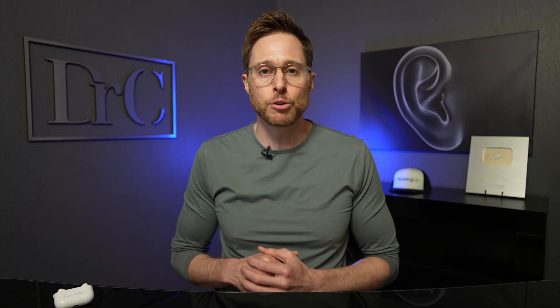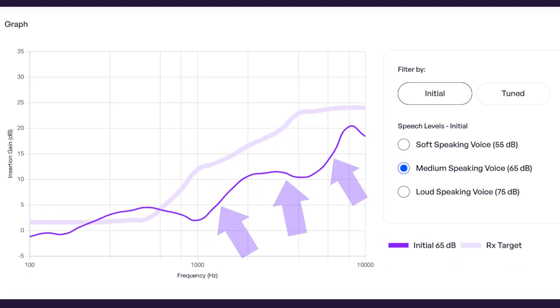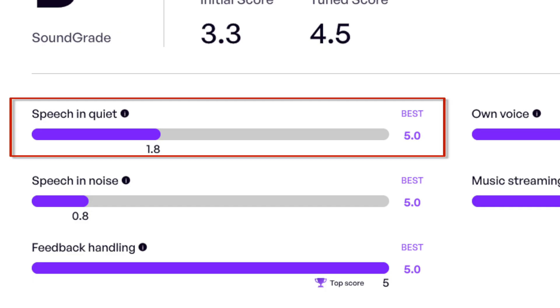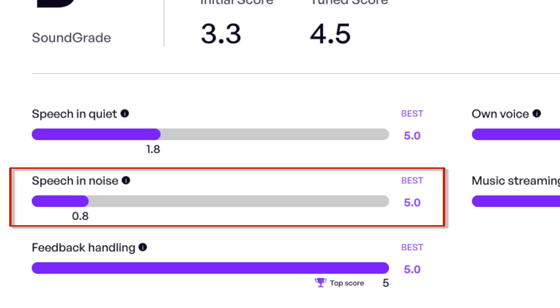Unfortunately, this is a chronic issue that we consistently measure with the Apple AirPods Pro 2 set up as hearing aids, and we're not the only people to identify this. This finding was also identified by HearAdvisor, an independent third-party hearing aid testing lab. Their initial testing showed significant under-amplification of sound above 630 Hz when in these initial first-fit settings — and keep in mind, we're trying to reach up to 8,000 Hz. This resulted in an initial performance score of only 3.3, with terrible performance in speech in quiet, and one of the worst scores ever recorded by HearAdvisor of just 0.8 out of 5 in speech-in-noise testing.